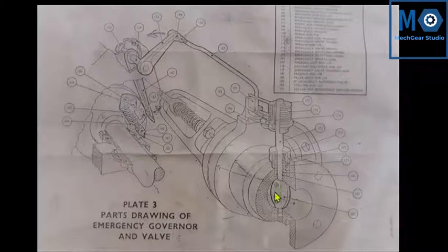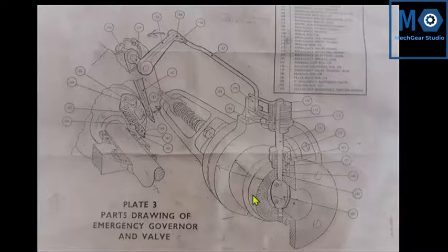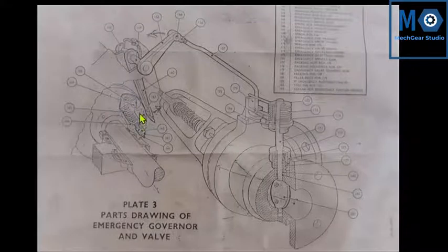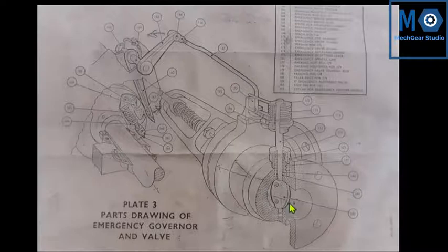In normal condition, this disc is similar to the throttle body of the carburetor — this disc always remains parallel so flow can take place easily. But when the emergency governor is operated, this disc comes to the perpendicular direction, so we can totally stop the steam flow. This disc is nearly the diameter of this pipe, so the emergency governor operates beyond some emergency RPM — when it operates, it will stop completely the steam supply.